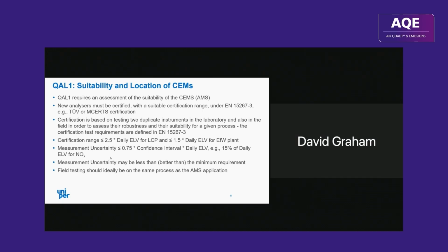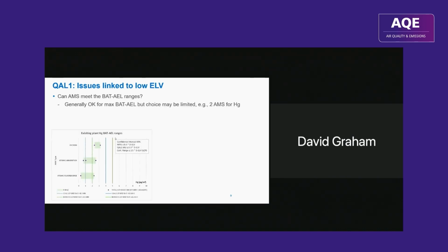Field testing should ideally be on the same process as the process to which the SEMS is applied. But ultimately, the plant operator is responsible for selecting suitable AMS or CEMS. So what are the issues linked to lowering emission limit values? Well, first of all, can the AMS meet the BAT-AEL ranges? This is an example for mercury.